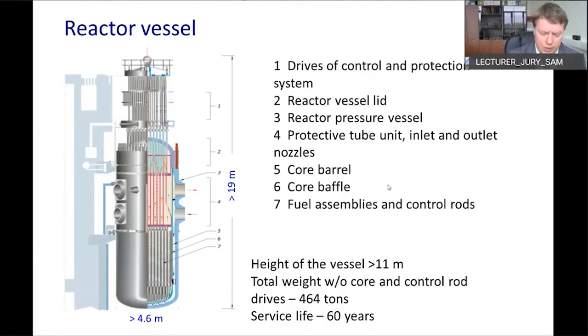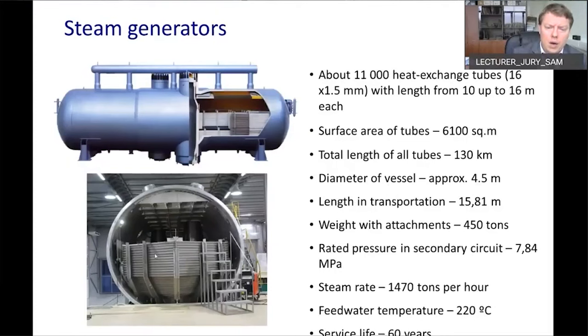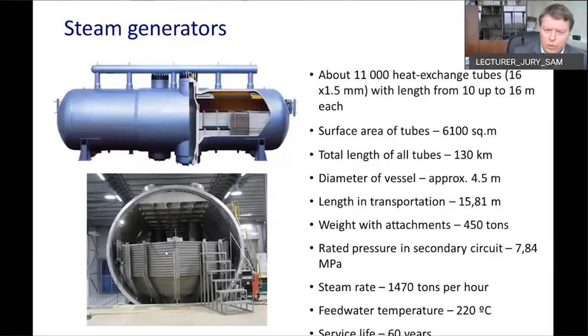After that, the heated water goes through outlet nozzles to the steam generator. The steam generator is huge equipment — the total tube surface area inside the steam generator equals approximately 12 football fields. Its design service life is more than 60 years, the same as the reactor vessel.